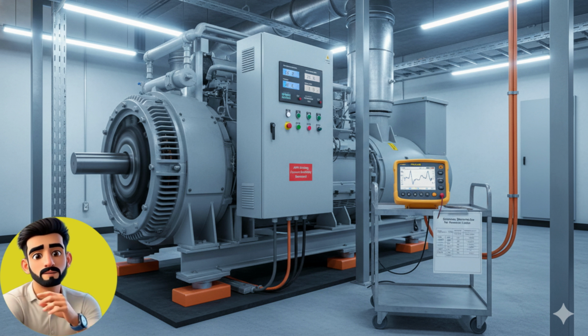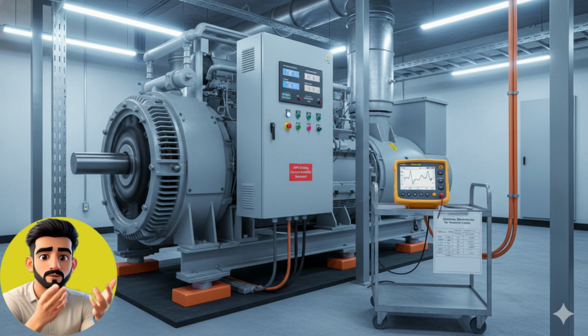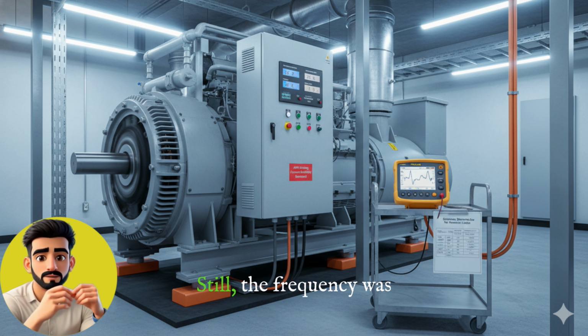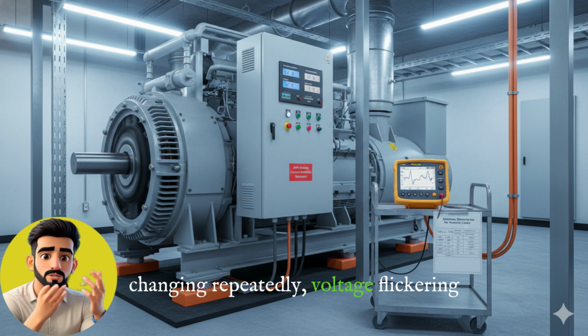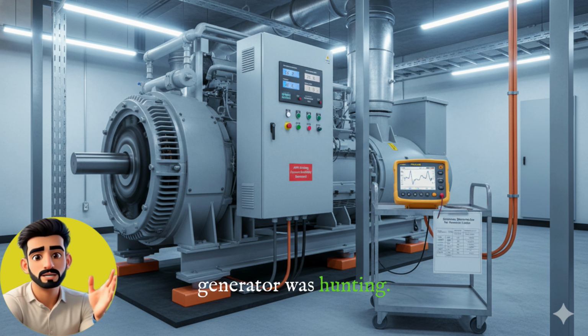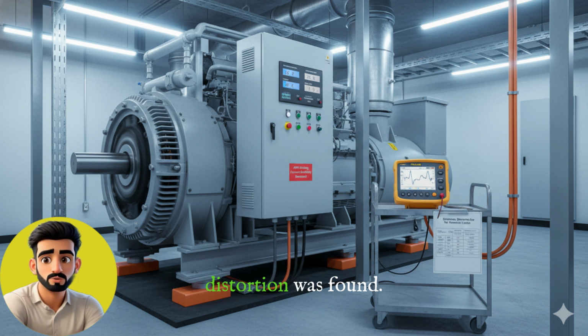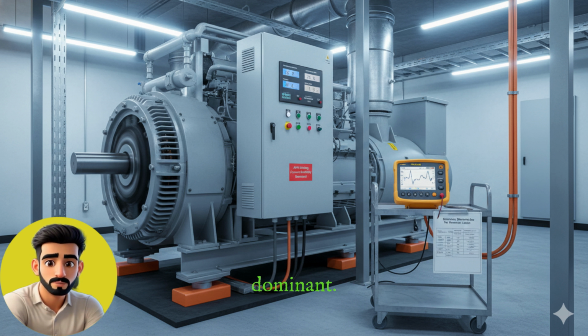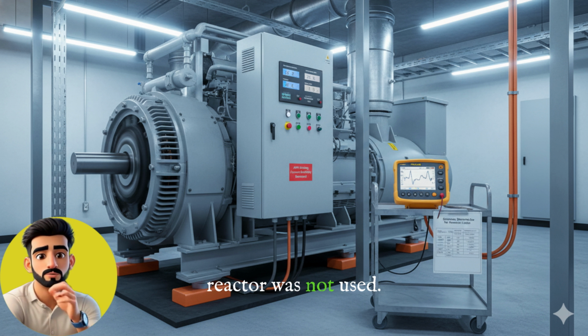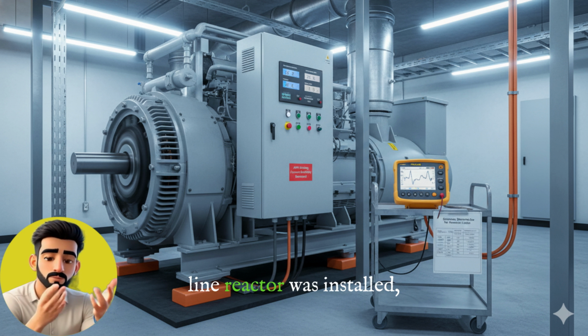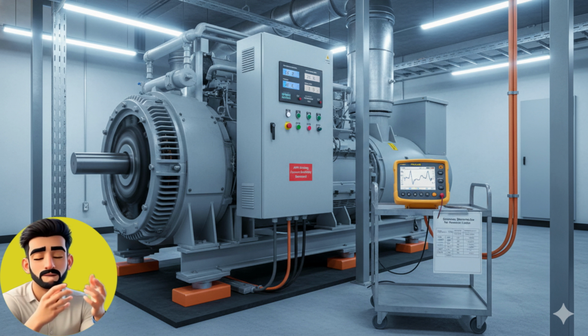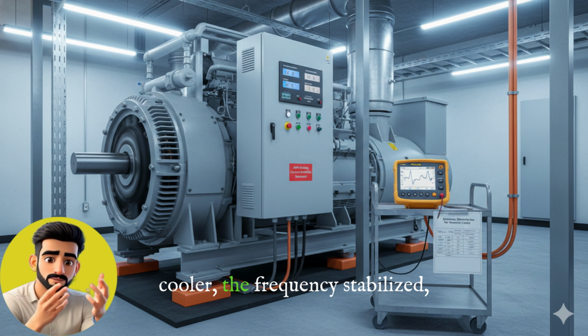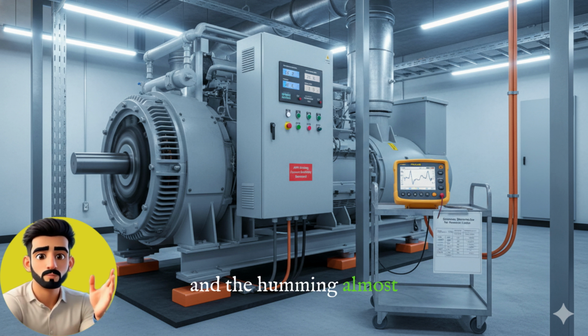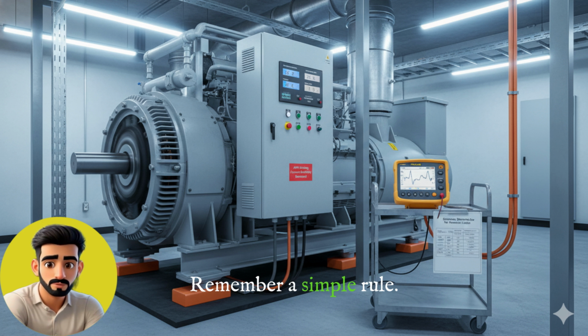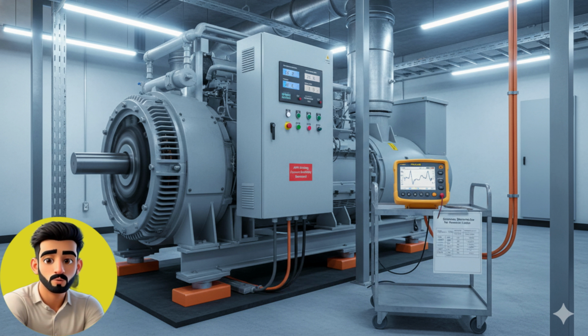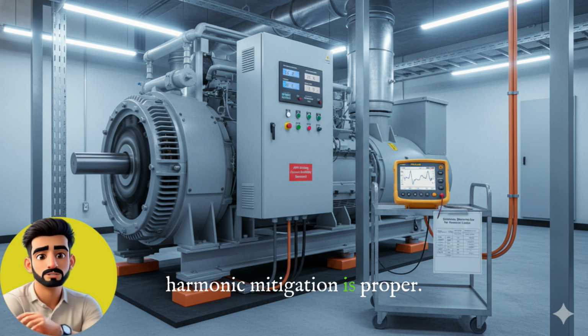Understand a real example. An 800 kVA generator was only half loaded. Still, the frequency was changing repeatedly. Voltage flickering was occurring and the generator was hunting. Upon checking, high current distortion was found. The fifth harmonic was dominant and the input line reactor was not used. As soon as the line reactor was installed, the system calmed down. The generator started running cooler. The frequency stabilized and the humming almost disappeared. Remember a simple rule: generator and VSD are only safe together when harmonic mitigation is proper.